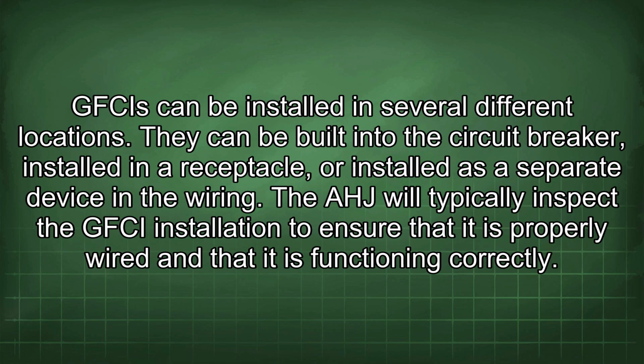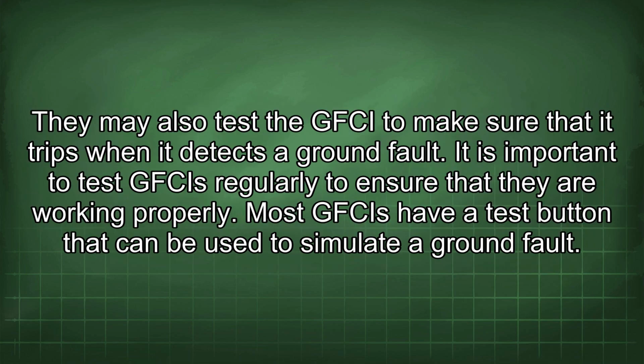If it is, the diagram will specify the location of the GFCI and how it should be wired into the circuit. GFCIs can be installed in several different locations. They can be built into the circuit breaker, installed in a receptacle, or installed as a separate device in the wiring. The AHJ will typically inspect the GFCI installation to ensure that it is properly wired and that it is functioning correctly. They may also test the GFCI to make sure that it trips when it detects a ground fault.